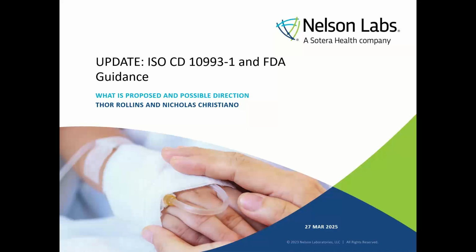But I get a lot of people who also question, could the worst case actually be in the middle? Like maybe you have something break down that exposes and then it gets washed away later. I think there's a lot of potential questions there. But right now what I see people doing is just doing repeat cycles until they get to an end of life and then perform biocompatibility evaluations. And by the way, that doesn't necessarily mean testing, like animal testing again. It could mean, once again, the chemistry stuff we talked about, just evaluating what could happen to the materials over time, look at detergent residuals, things like that.